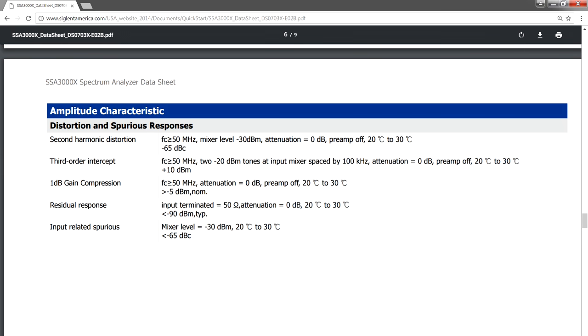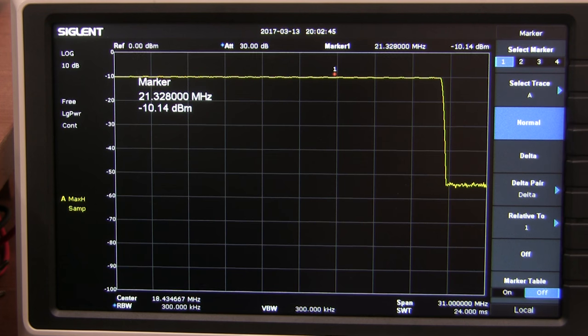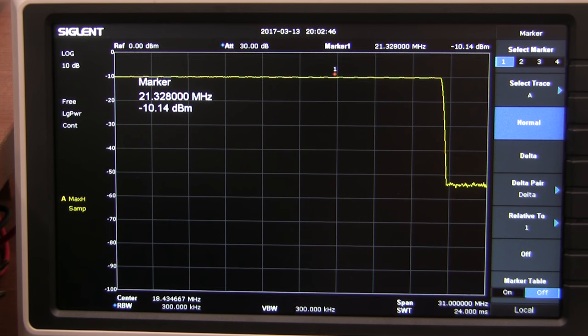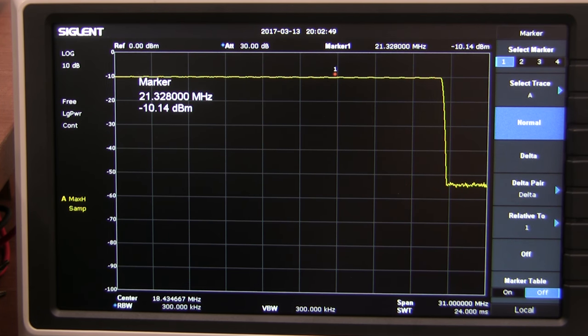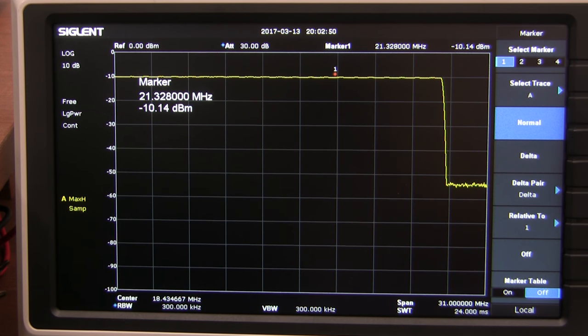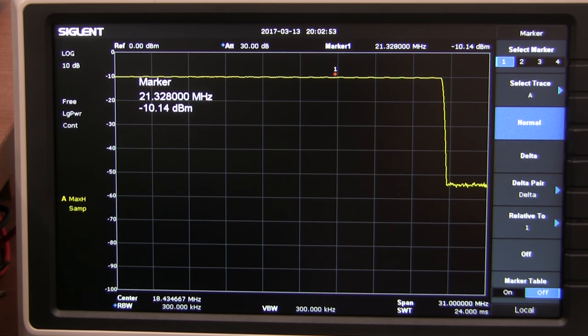As annoying as these are, they are within the specifications of the datasheet, and every spectrum analyzer has them in some form or another. Just because a review doesn't talk about spurs, it doesn't mean that they're not there. For what it's worth, I'm seeing a lot fewer spurs than I get on my Signalhound SA44B. Moving on, the amplitude accuracy is stated to be within 0.7 dB. I can only test that at lower frequencies, but my minus 10 dBm test sweep was exactly as flat and accurate as I was hoping it would be.